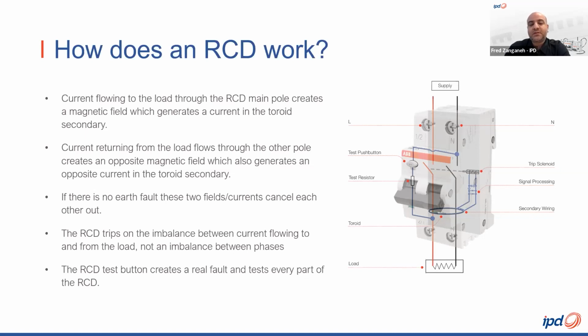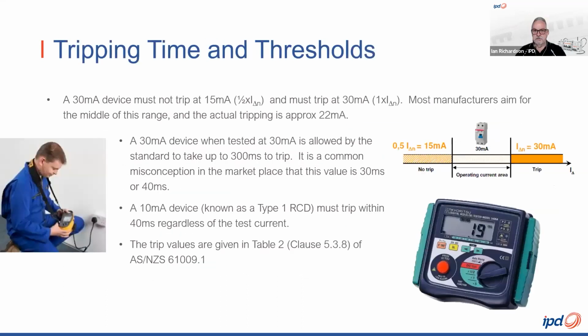So Ian, what do the standards say about the sensitivity of RCDs for people protection? Very good question, Fred. The standards tell us a 30 milliamp device must not trip at 15 milliamps or 50% of its sensitivity. But it must trip at 30 milliamps or 100% of its sensitivity. And this is typical of the way a standard could be written. Most manufacturers aim for around the middle of this range, and the actual tripping is approximately 22 to 25 milliamps. A 30 milliamp device, when tested at 30 milliamps, is allowed by the standard to take up to 300 milliseconds to trip.